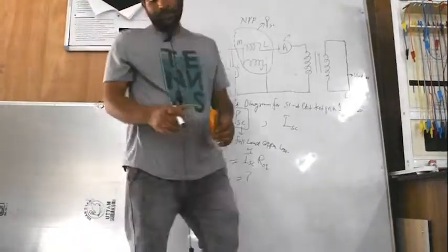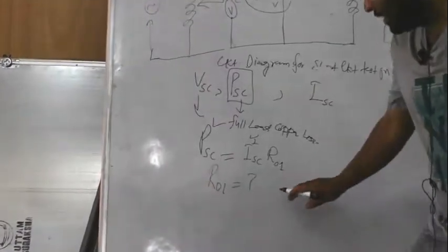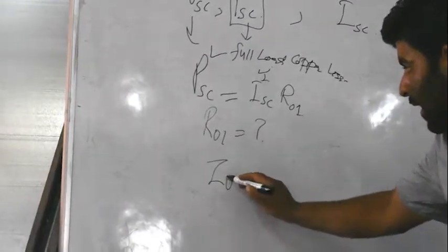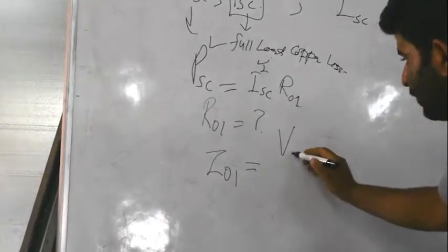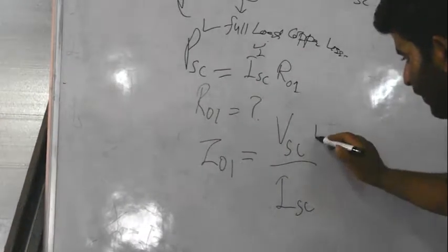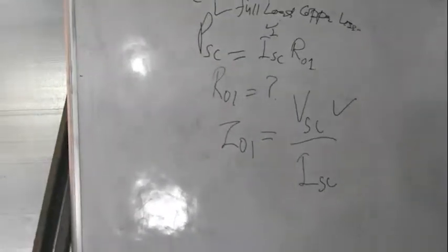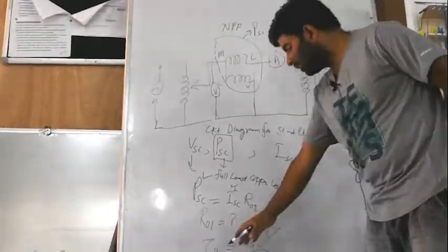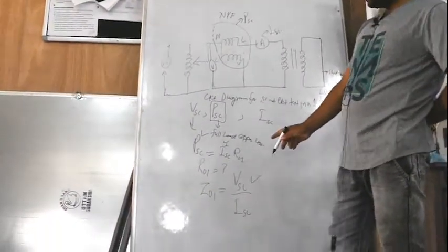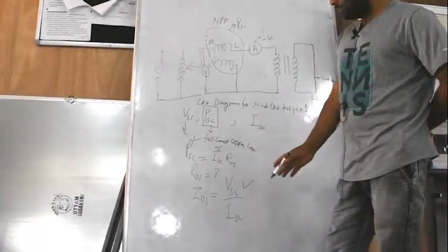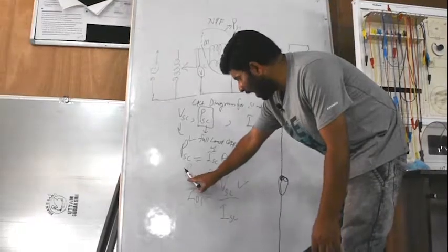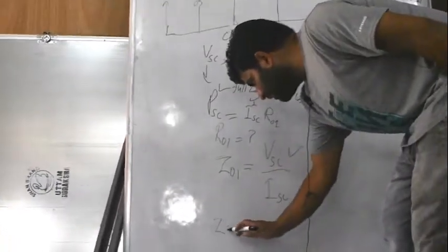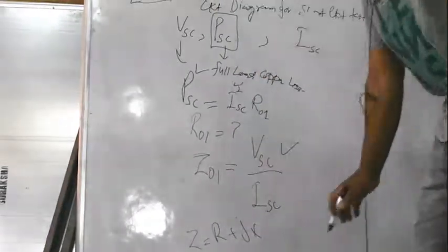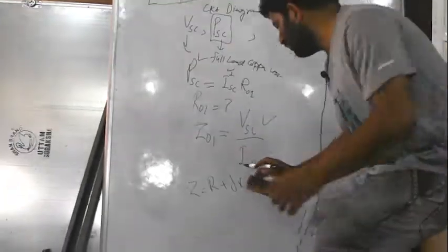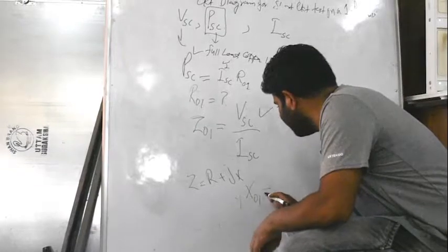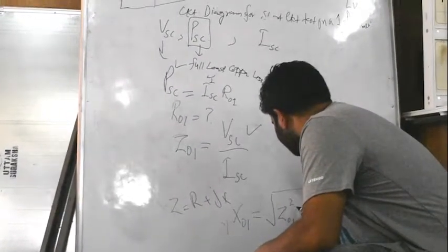Knowing the equivalent resistance, what you are left with is the equivalent reactance, right? First we calculate the equivalent impedance as referred to this side, which is the ratio of VSC by ISC, simple. You have the VSC reading from this meter and the ISC reading from this meter, so you can obtain the equivalent impedance Z01. This equivalent impedance is the phasor sum R plus jX. So knowing the magnitudes of R01 and Z01, we can obtain the reactance X01 as the square root of Z01 square minus R01 square.